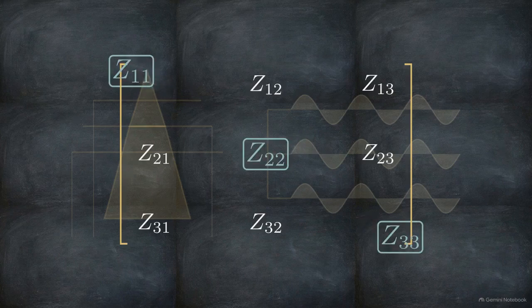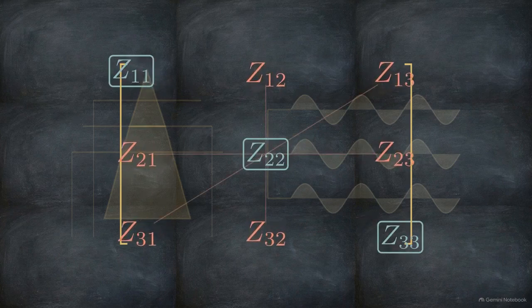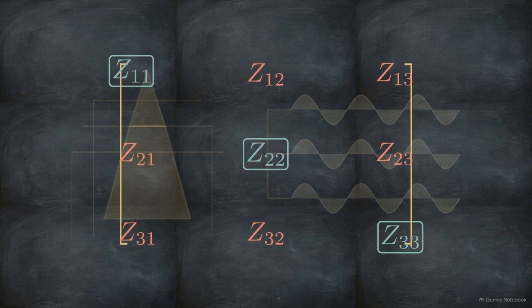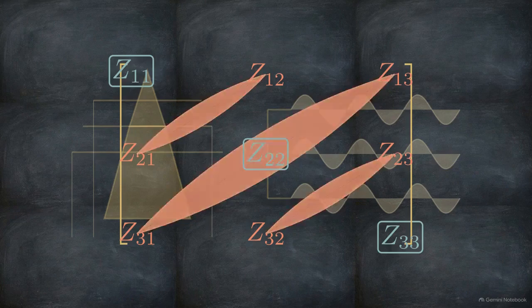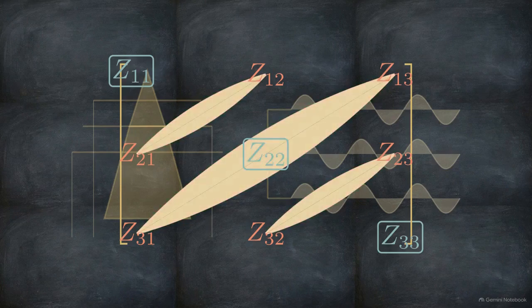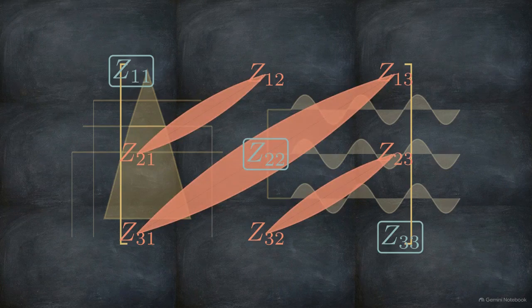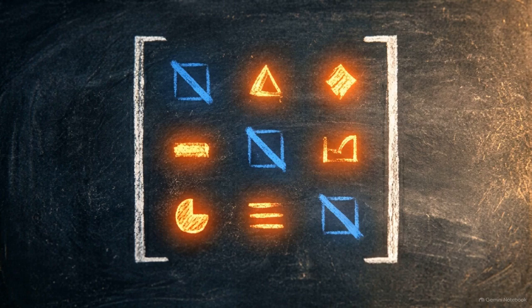The values on the diagonal represent the self-impedance of each wire, but the off-diagonal terms represent the mutual inductive coupling between phases. A change in phase A instantly affects phase B, locking equations together. To break this lock, the system requires circular symmetry, meaning the diagonal terms must equal each other, and all mutual off-diagonal impedances must be identical.